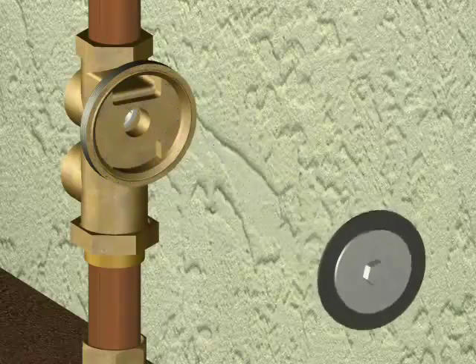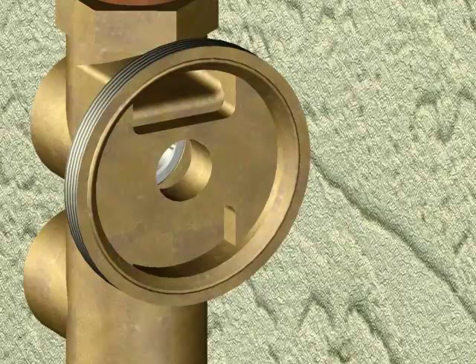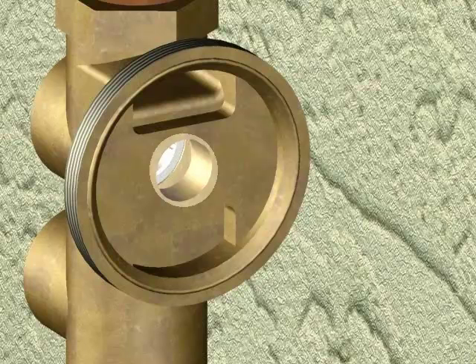Remove the stem assembly. Inspect the area in the body where the O-ring moves for pitting or scratches. This area must be smooth for the valve to operate correctly. You can sand the bore with an emery cloth if needed.